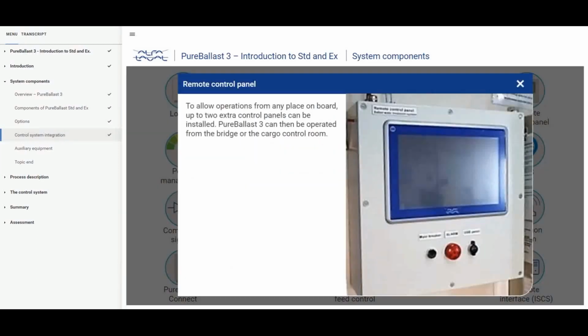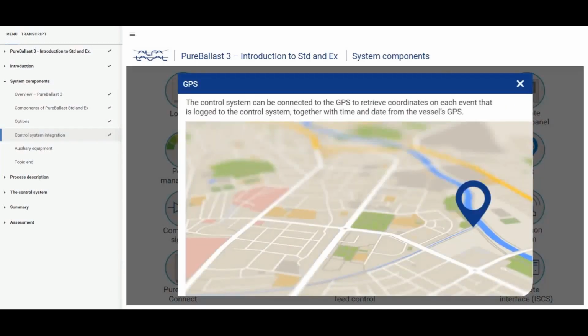To allow operations from any place on board, up to 2 extra control panels can be installed. Pure Ballast 3 can then be operated from the bridge or the cargo control room. The control system can be connected to the GPS to retrieve coordinates on each event that is logged to the control system, together with time and date from the vessel's GPS.